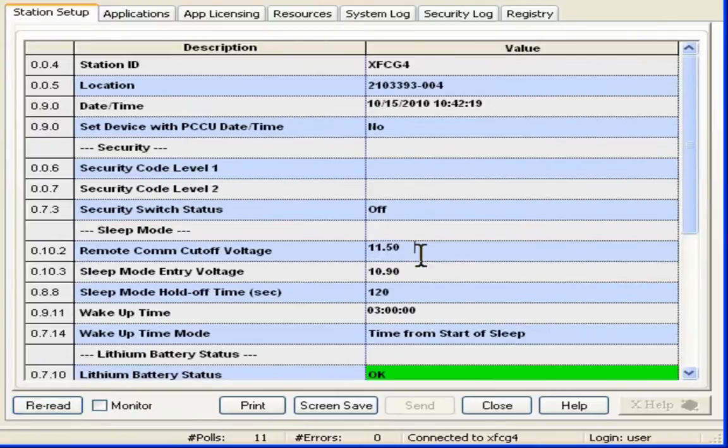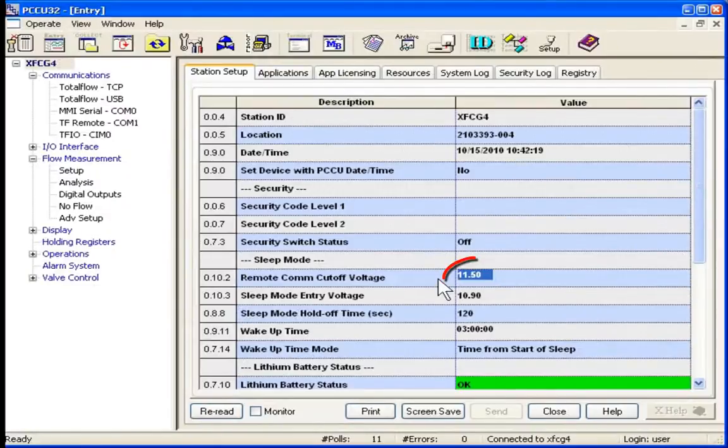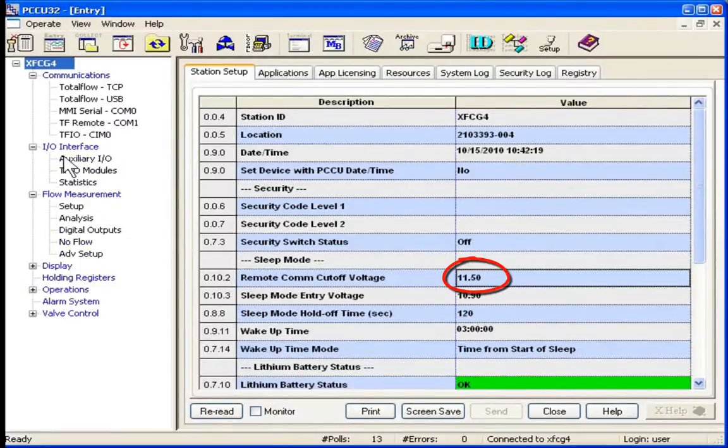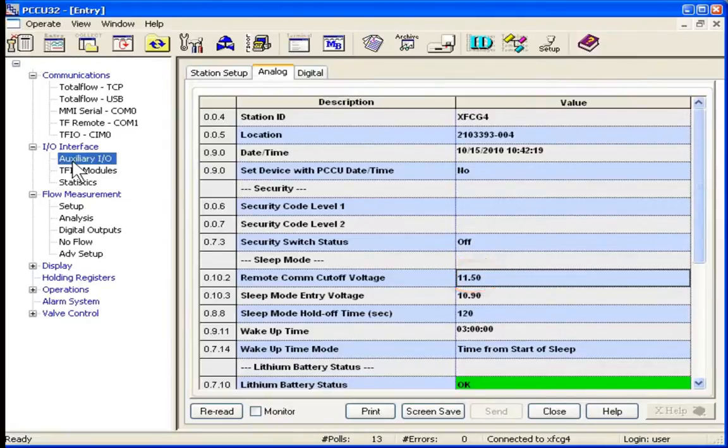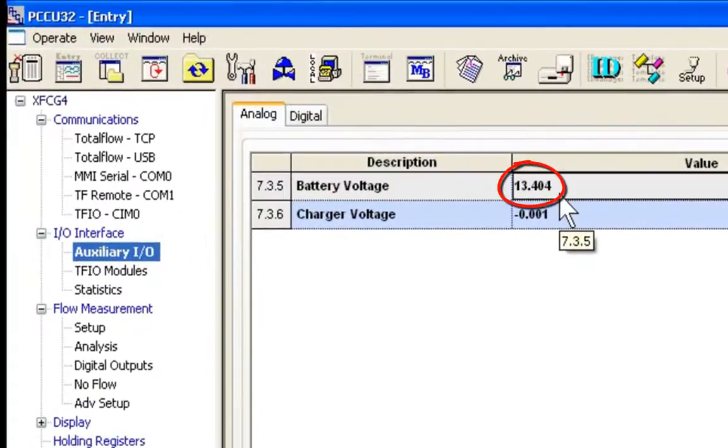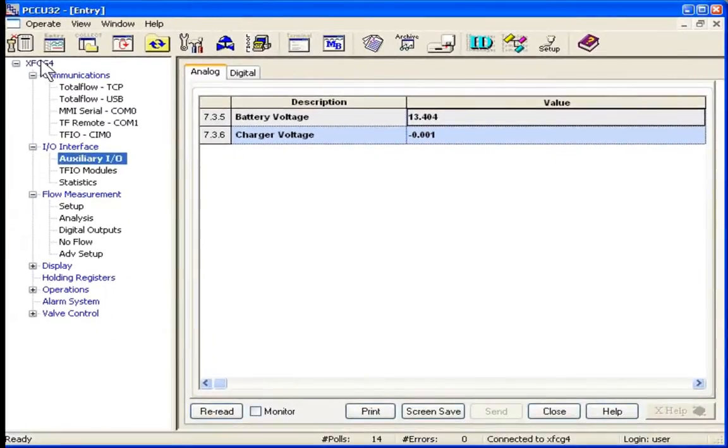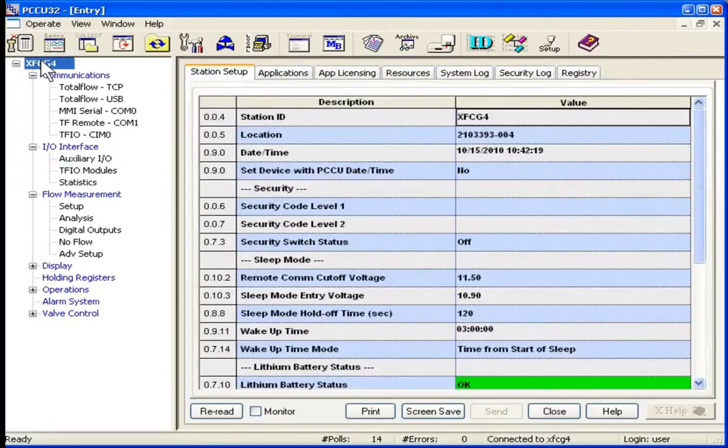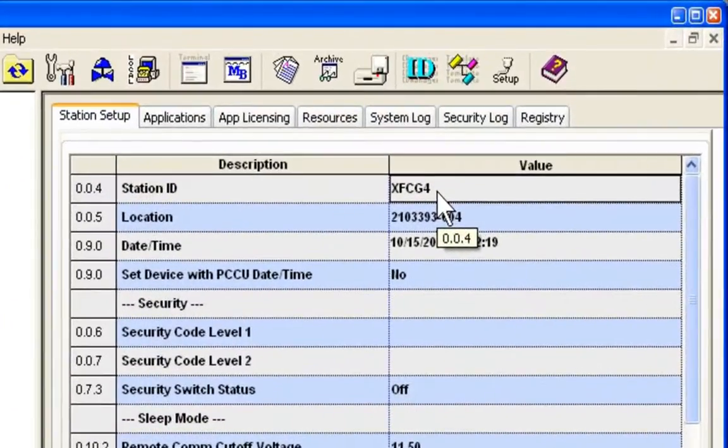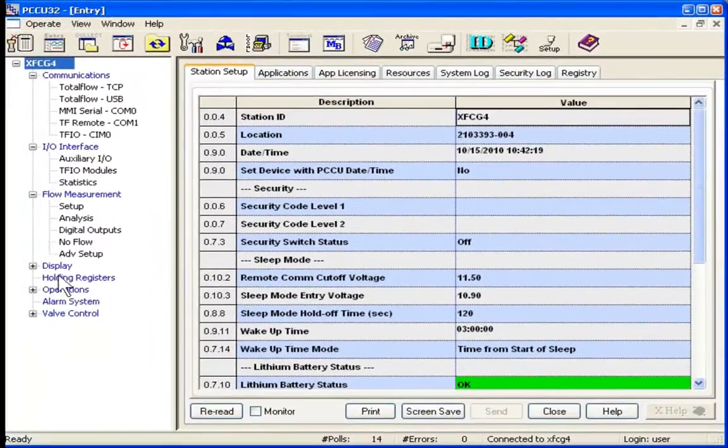Next we will take a look at the remote comm cutoff voltage. We want to make sure we have sufficient voltage that our remote communications will not be interfered. We see that we have 13 volts, which is above the 11 and a half that we have as the parameter. Next let's verify the ID for communications. Make sure that we know exactly what the station ID is. So we've verified that. That looks good.